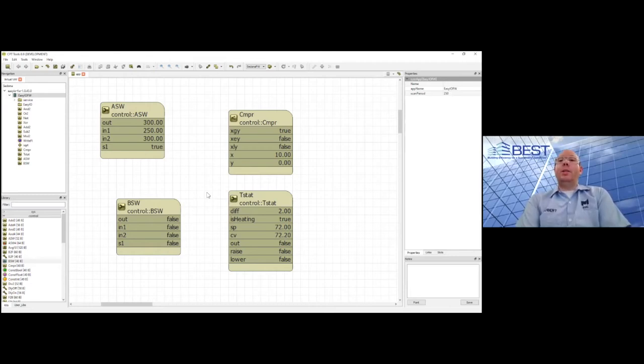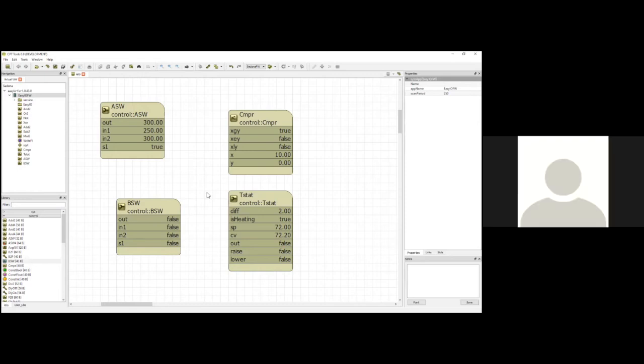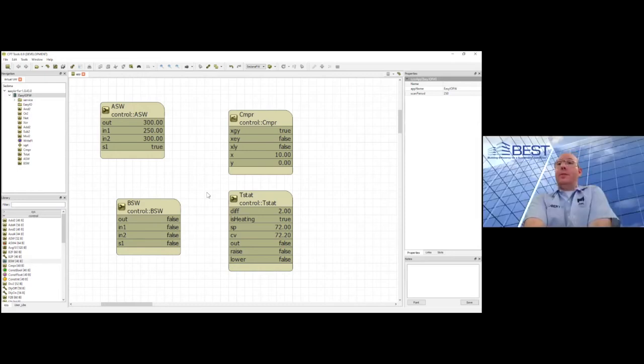So what Bob is talking about is we just installed our FW math kit. If somebody walks up with a different computer that for whatever reason does not have that FW kit or FW library installed on their computer or available in the Sedona data folders, they will not be able to connect to that controller. And actually that's kind of a sneaky backdoor way for companies to lock other companies out of a given controller.